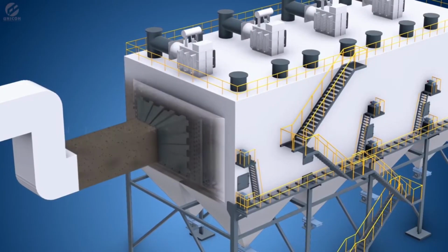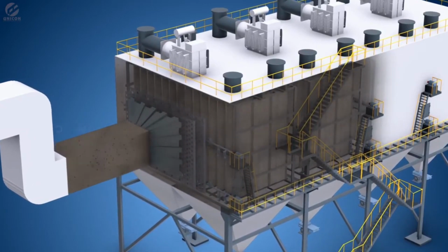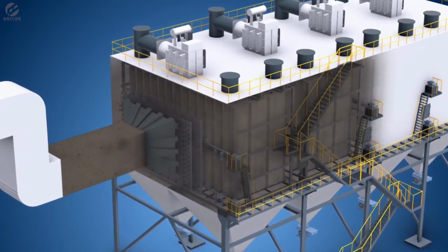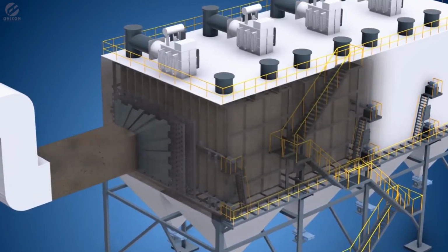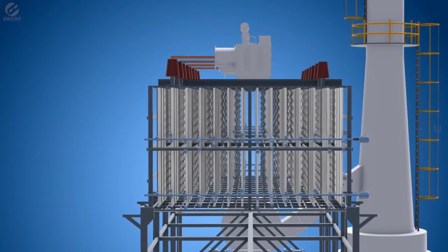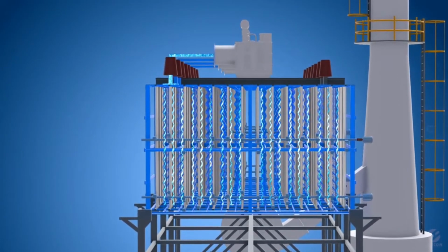The flue gas along with suspended particle enter the ESP through the CFD optimized splitter and GD screen, which evenly distribute the flue gas across the entire ESP. The emitting electrodes in the center of gas flow is maintained at high voltage.